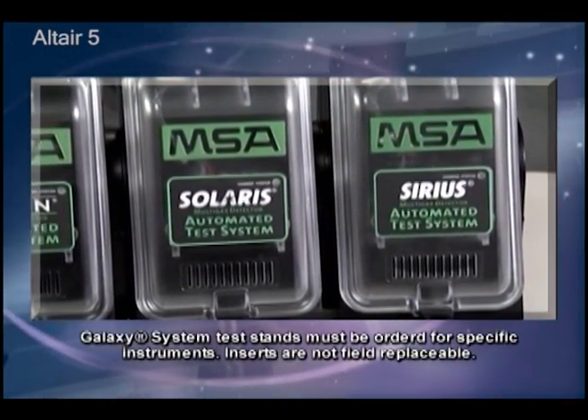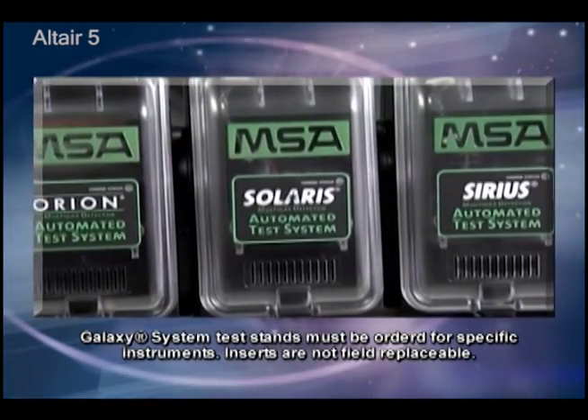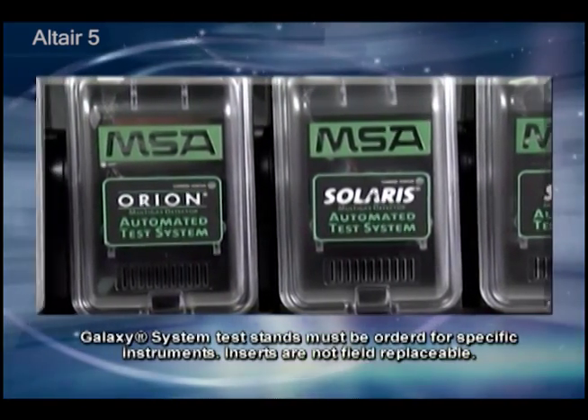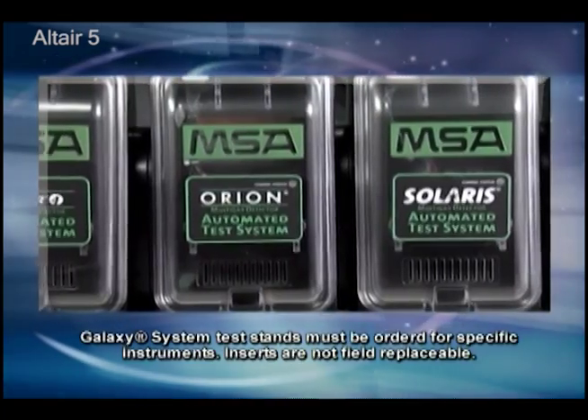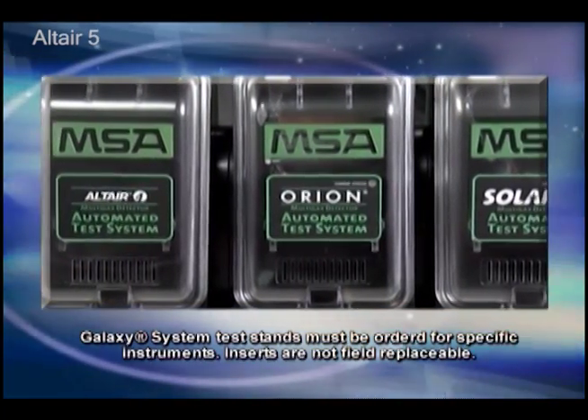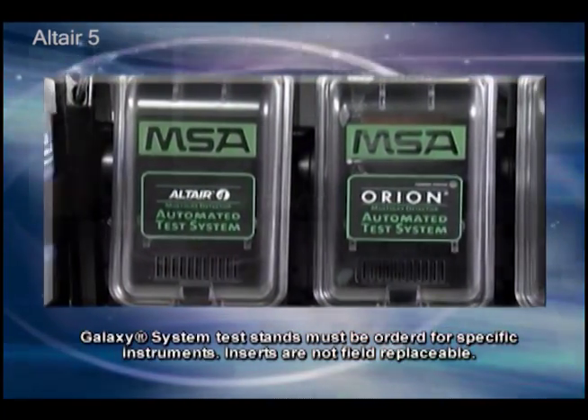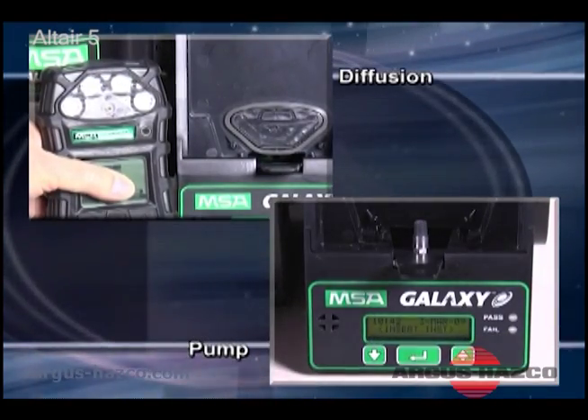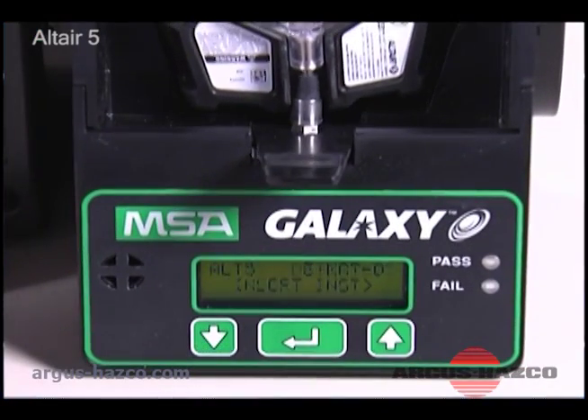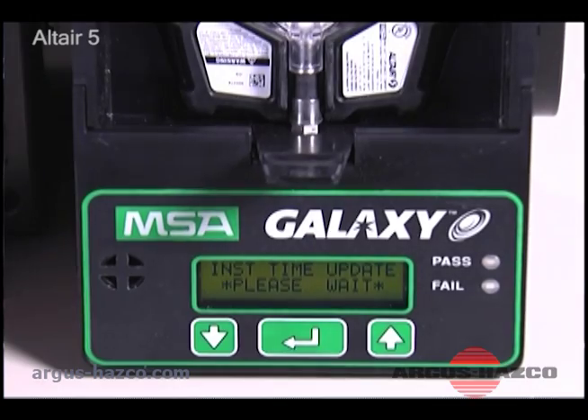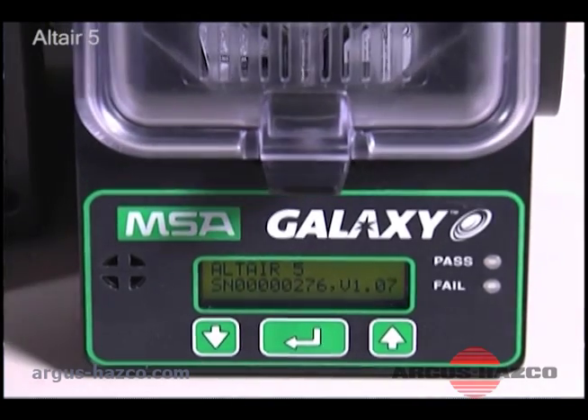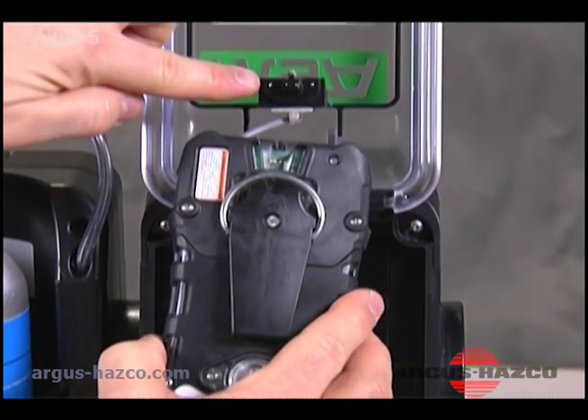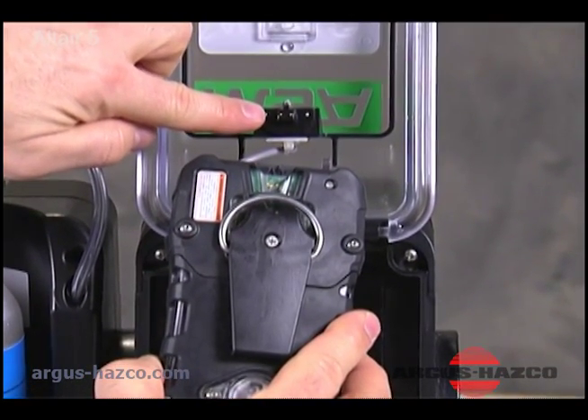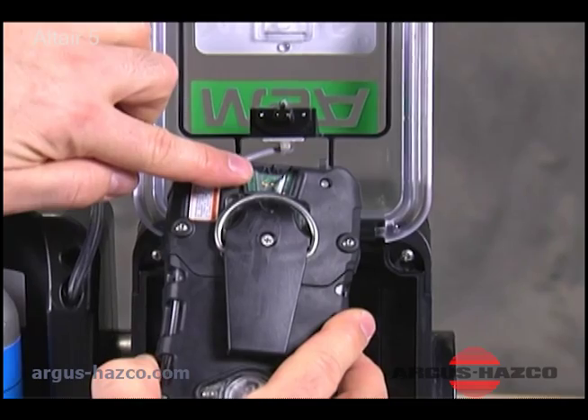Special inserts adapt the Galaxy system to test MSA Altair 4, Altair 5, Altair Pro, Orion, Solaris, and Sirius gas detection instruments. The Galaxy system automatically identifies an inserted instrument, verifies calibration, bump tests, and calibrates, and stores calibration data. A charging circuit recharges units equipped with nickel metal hydride or lithium-ion batteries.